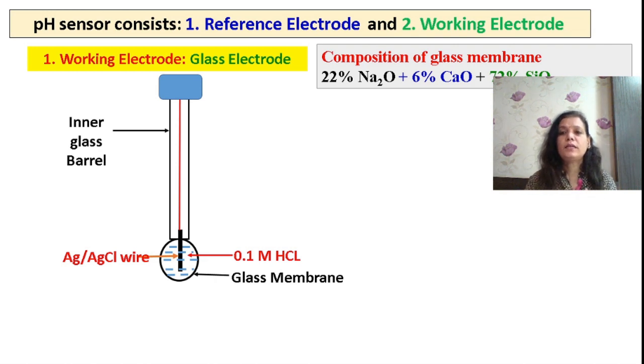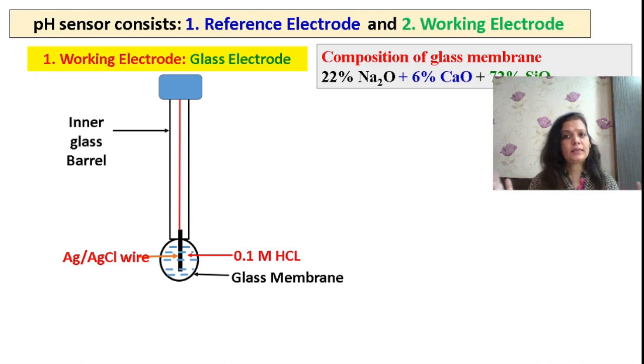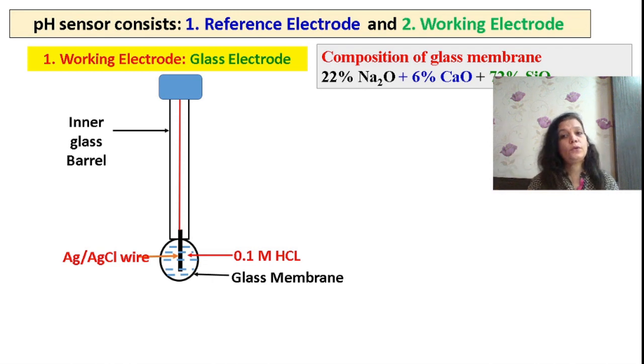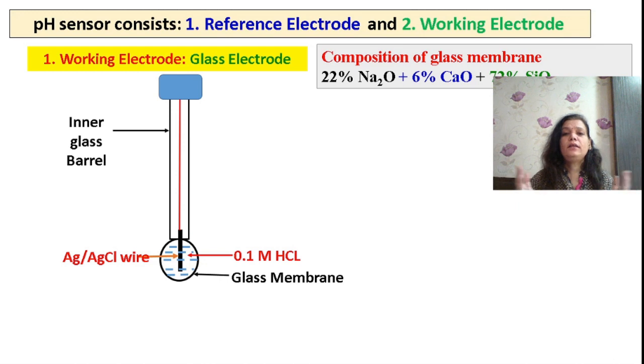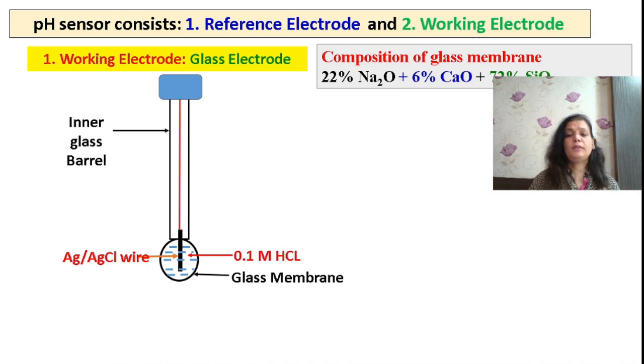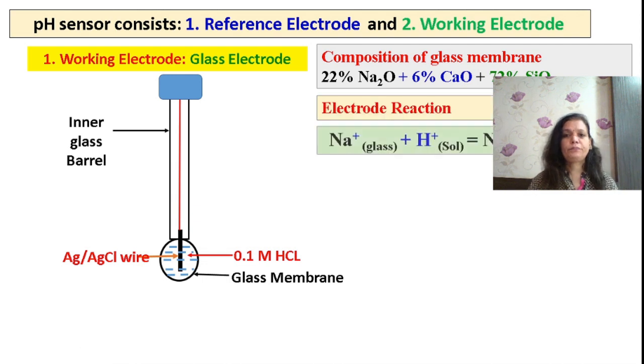The composition of the glass membrane is very important. It is made of sodium, calcium, and silicate, and this defines the working range of the glass electrode — it functions in the pH range of 0 to 12. The pH scale correlates with the dissociation of water, with Kw equal to 1×10⁻¹⁴. By modifying the composition with the addition of lithium, the working range can be extended up to pH 14.